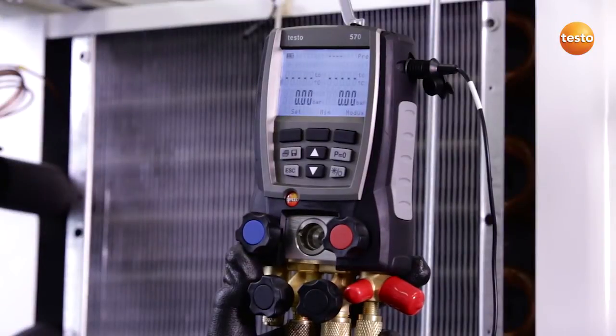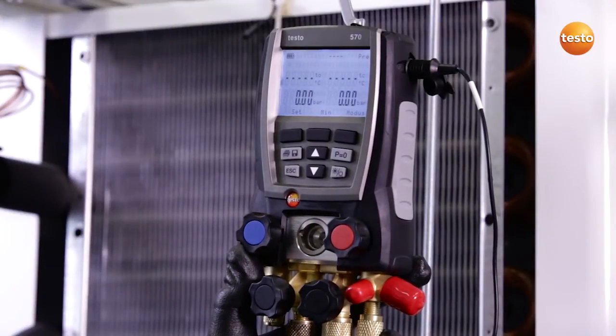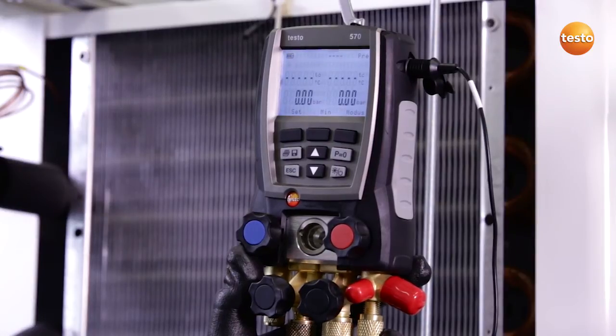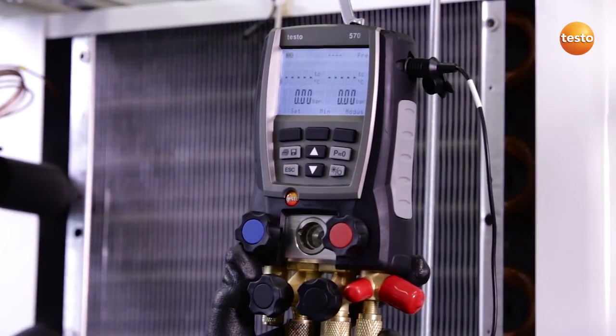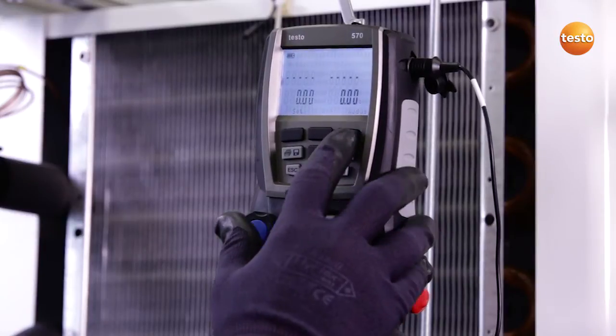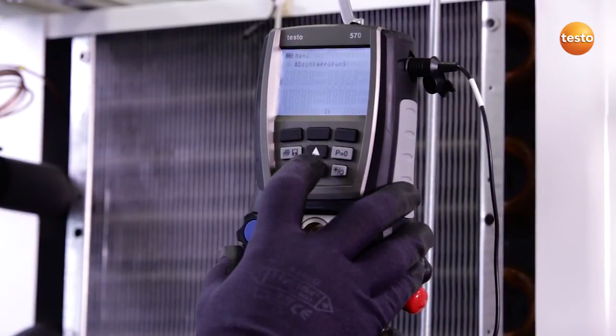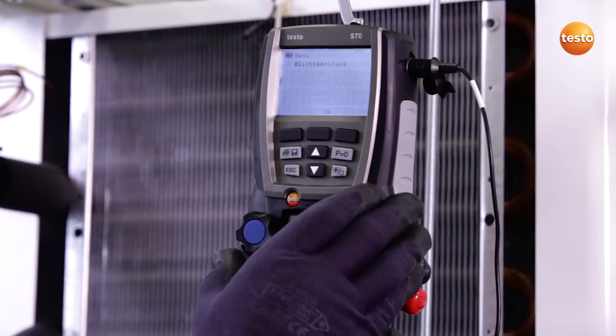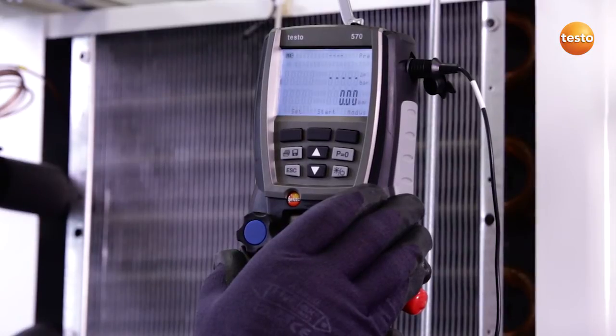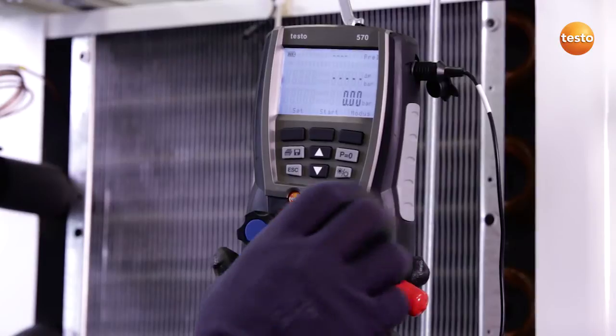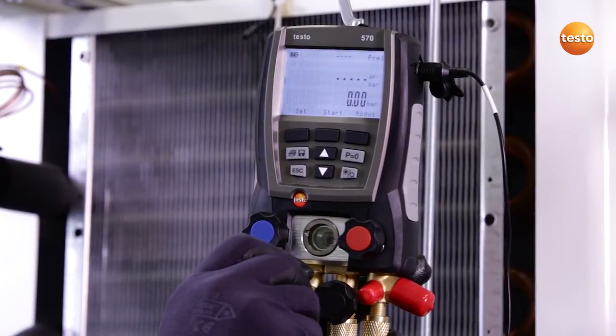According to the specification plate on the plant, the maximum positive operating pressure is 6 bar. In order to ensure these 6 bar, I will now switch the instrument mode over to tightness test and release the pressure to the system.